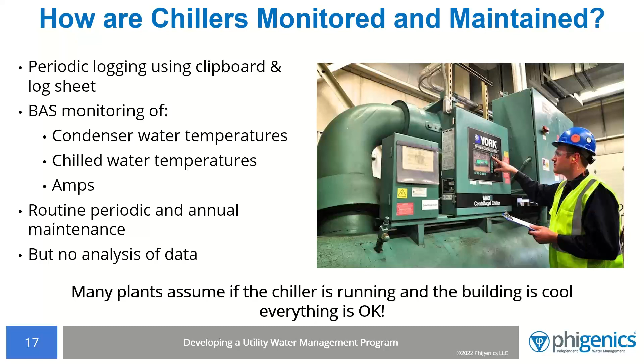But in the majority of facilities we see, there is no analysis of all the data collected, no matter how it's collected, that shows you where you are on the continuum between operating your chillers at design efficiency or operating your chillers at the ragged edge of efficiency or even failure. Your chiller can be running fine and still be 10%, 15% inefficient.